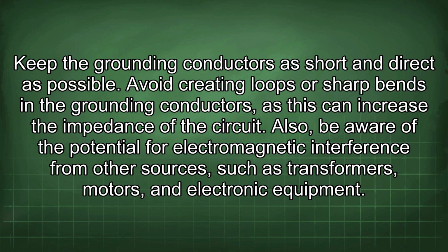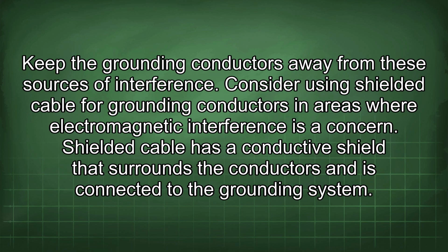Also, be aware of the potential for electromagnetic interference from other sources, such as transformers, motors, and electronic equipment. Keep the grounding conductors away from these sources of interference. Consider using shielded cable for grounding conductors in areas where electromagnetic interference is a concern.